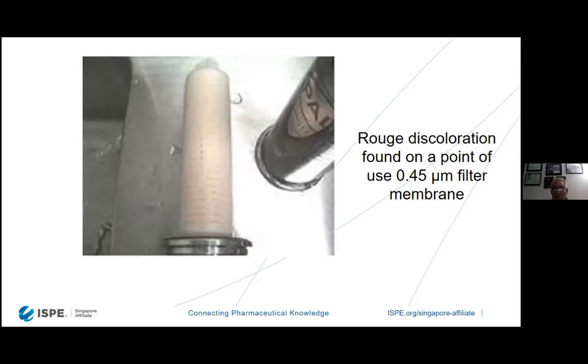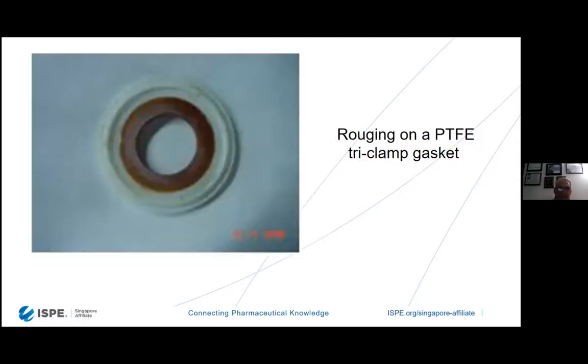Unfortunately, most people don't put them there because of a guideline that came out almost 40 years ago through the FDA. What the FDA said is you cannot use membranes specifically for microbial, but you can use them to stop particulates or whatever. So a lot of people don't even use membranes, but they can. And 0.22 or 0.45 are excellent at stopping particulate rouge from migrating across the system. What many people don't know is that gasketing and non-metallic gasketing like PTFE, ETFE, PVDF, et cetera, all have a slight negative charge. And rouge, which is coming as a particulate through the system, is a positive charge. And what will happen is that those filters and that material, even nylon, can attract those particulates, and they can be embedded even in a non-metallic gasket, like you're seeing here with PTFE.